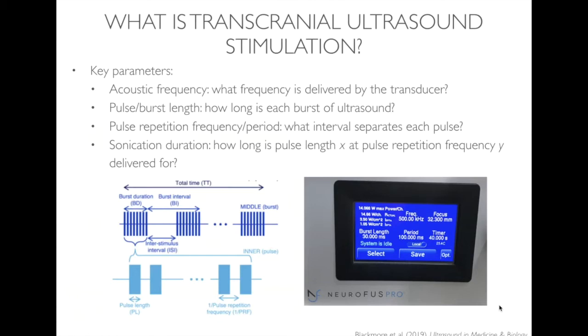I'll go into how you calculate that a bit later on. You've also got something called the sonication duration, illustrated by the darker blue columns along the top. The sonication duration is: how long is each pulse train, repeated at the pulse repetition frequency, delivered for? So how long are the bursts of pulses delivered for? That's called the sonication duration or burst duration.